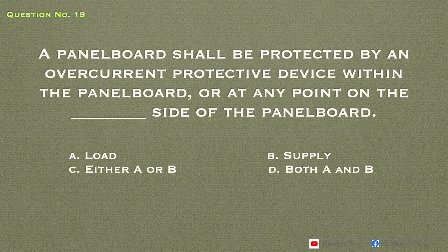Question number 19. A panel board shall be protected by an overcurrent protective device within the panel board or at any point on the blank side of the panel board. A. Load. B. Supply. C. Either A or B. D. Both A and B. Answer B. Supply.